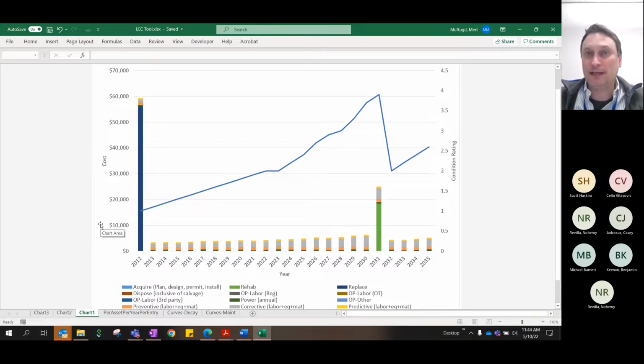However, you can also be plotting, if you have an idea of what the consequence of failure rating is for this asset, and you've gone through some of those steps to express it in terms of a dollar value. Imagine you can actually be putting a monetized risk against this cost line as well. So if the asset's failure is going to cost us about, let's say, $30,000 worth of investment needs to remedy, we could actually plot how close we are as the asset ages to that number.